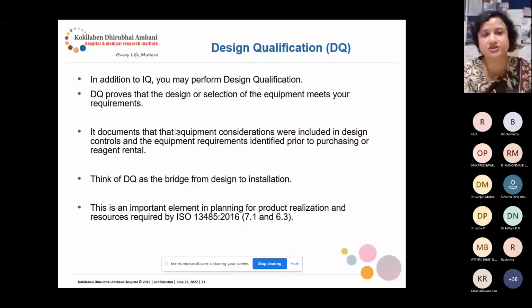In addition to IQ, we should perform design qualification. In an old lab we may not need so much design qualification, but it's always better: when an instrument is coming to our lab, redesign the process according to the lean process so that there is less movement and less rework, and the work is in a lean flow. DQ proves that the design or selection of the equipment meets your requirements, and it documents that the equipment considerations were included in design controls and the equipment requirements identified prior to purchasing or reagent rental. So think of DQ as a bridge from design to installation, and this is an important element in planning product realization and resources.